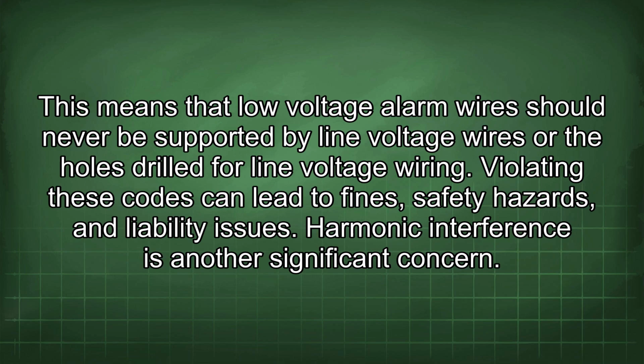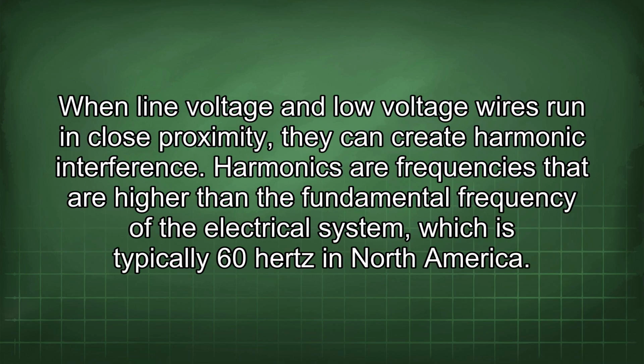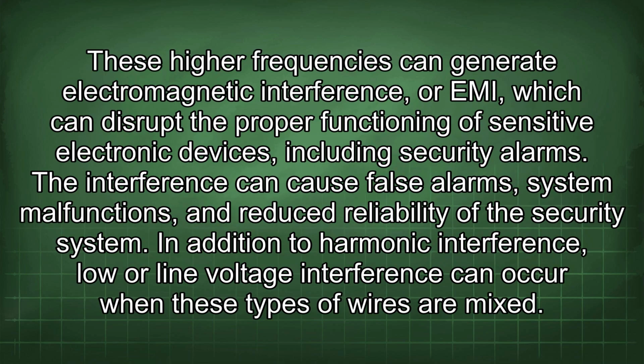Harmonic interference is another significant concern. When line voltage and low voltage wires run in close proximity, they can create harmonic interference. Harmonics are frequencies that are higher than the fundamental frequency of the electrical system, which is typically 60 Hz in North America. These high frequencies can generate electromagnetic interference, or EMI, which can disrupt the proper functioning of sensitive electronic devices, including security alarms. The interference can cause false alarms, system malfunctions, and reduced reliability of the security system.